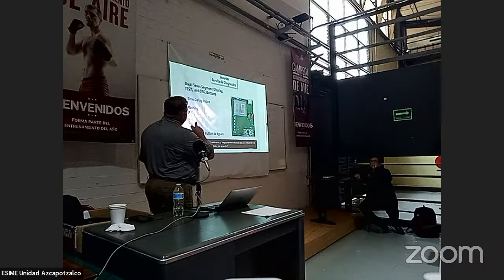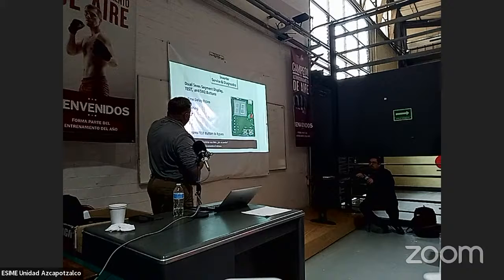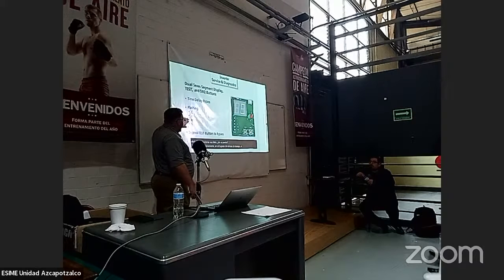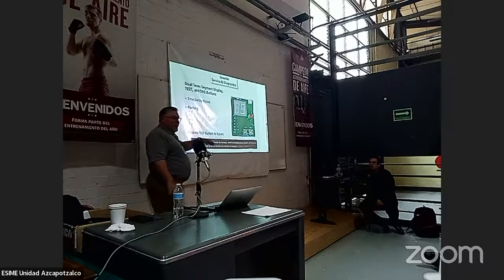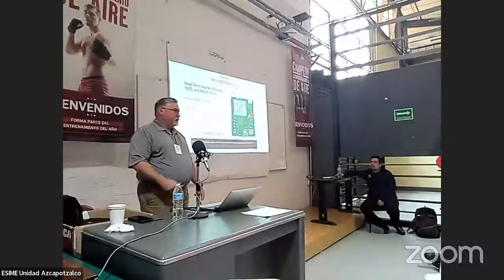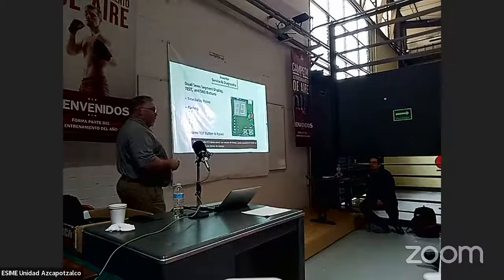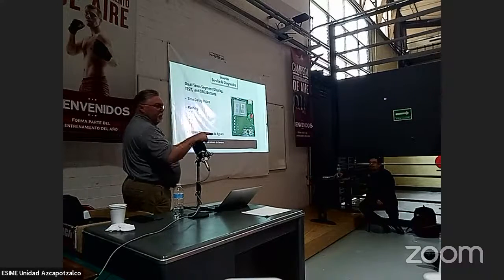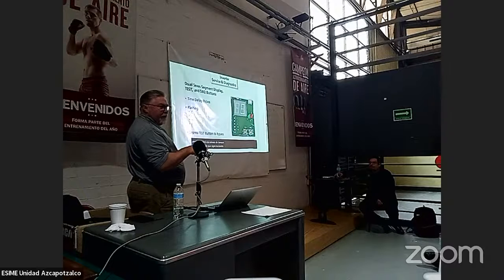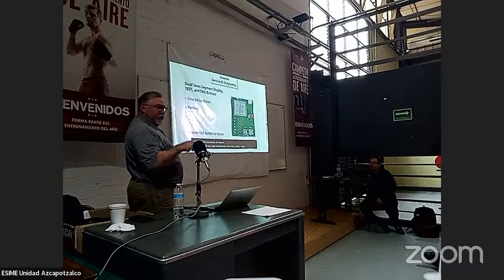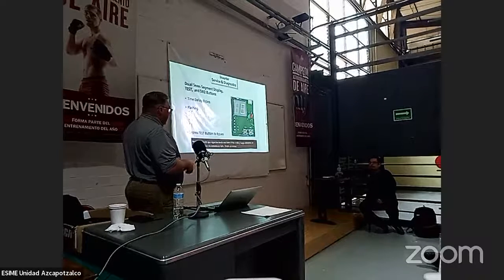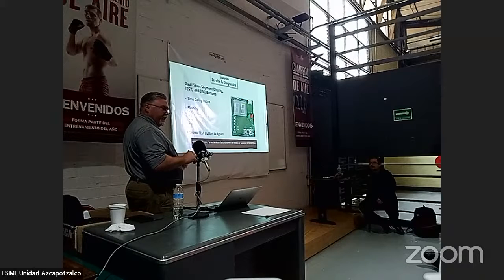Then, on the time delay bypass, those are your flashing big C, little c, big H, and little h. If you want to bypass that time delay, you press the test button, and it will bypass that time delay. Okay? I don't recommend you keep doing that. If it fails and then you get time delay, you reset it. Don't keep doing that. If it fails the second time, stop and figure out why it failed.